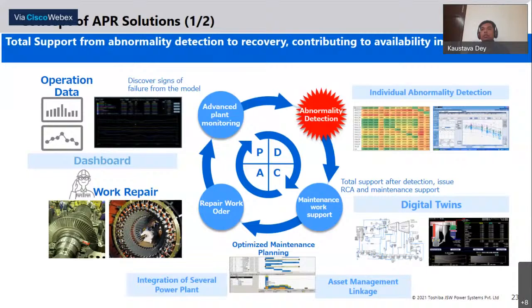In case any equipment's operating pattern deviates from its normal pattern, it will give us an abnormality detection. This abnormality detection is not similar to a DCS detection. It's different, depending on correlation based models. If any abnormality detection appears, it will intimate the plant O&M people. Then the maintenance work support will be required, and the repair work order generation will happen. After the repair is done, it will again go into monitoring mode.